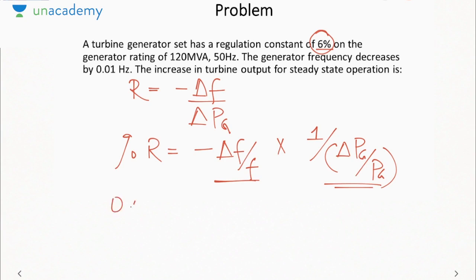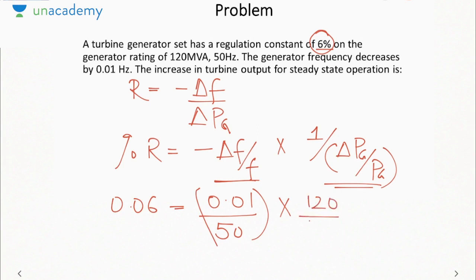Okay, so it is 0.06, change in frequency is 0.01, the actual frequency is 50, into generated power is 120. Delta Pg we need to calculate, so this will be removed. So delta Pg will be 0.4 megawatt. So here that means generated power will change by an amount of 0.4 megawatt, but with a change of 0.01 hertz in frequency.